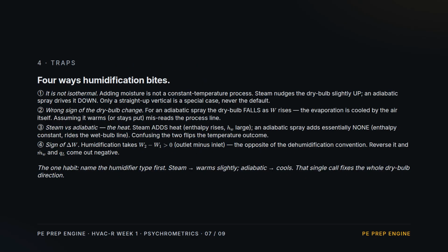Traps. 1. Humidification is not isothermal. Steam warms slightly, spray cools. 2. For an adiabatic spray, the dry bulb falls as moisture rises because the air pays the evaporation heat. 3. Steam adds heat. Adiabatic adds none. Confuse them and the temperature outcome flips. 4. Take humidity ratio outlet minus inlet, so delta W is positive, the opposite of the dehumidification sign.